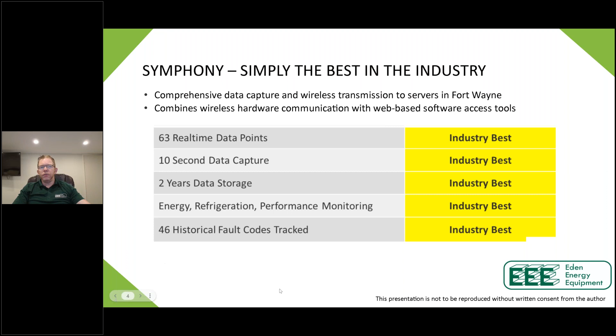It also means that as we see a lockout, we can look at every single condition, including what the unit was doing, what the call was, what the output to the unit was, and what the homeowner was doing. There's a lot that really comes into play here. The other essential thing is it tracks all the lockout codes too, so you can see if you're consistently having a communication error, or getting high pressure lockouts. The amount of data the system collects is very, very impressive, and a lot of thought has been put into how it's put together.